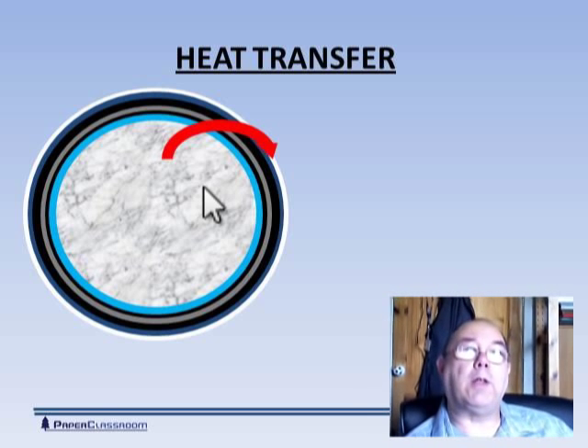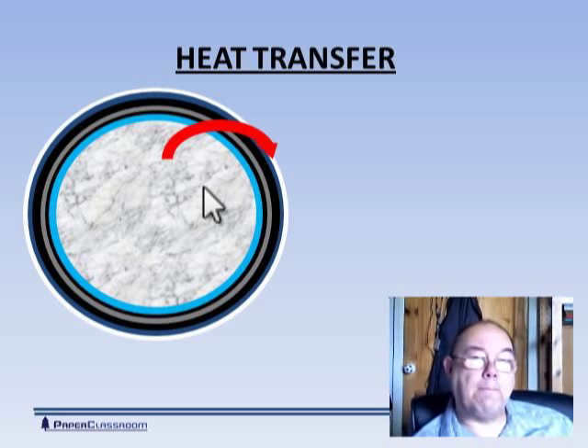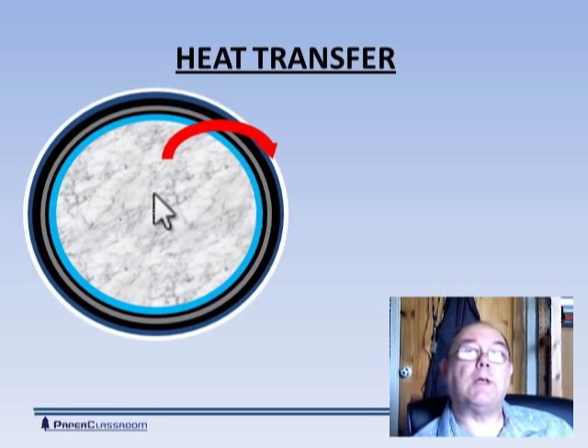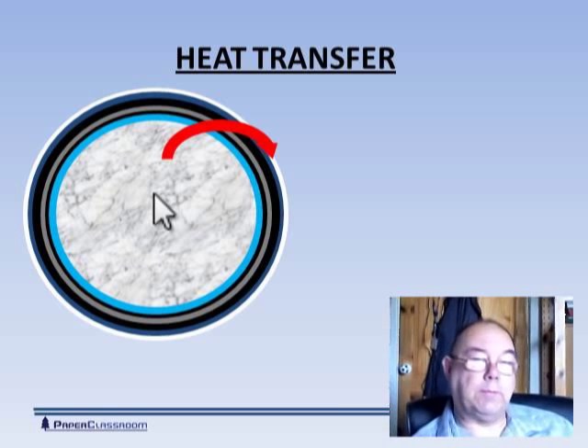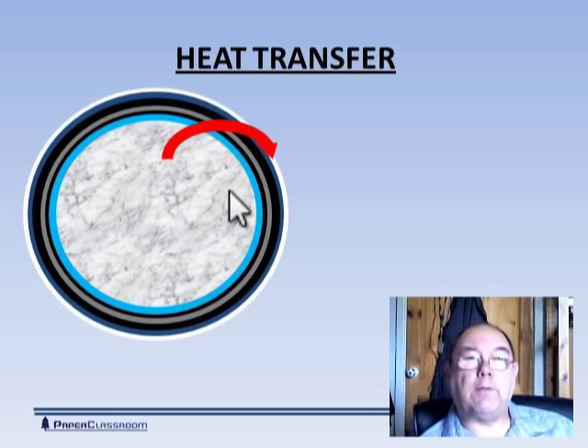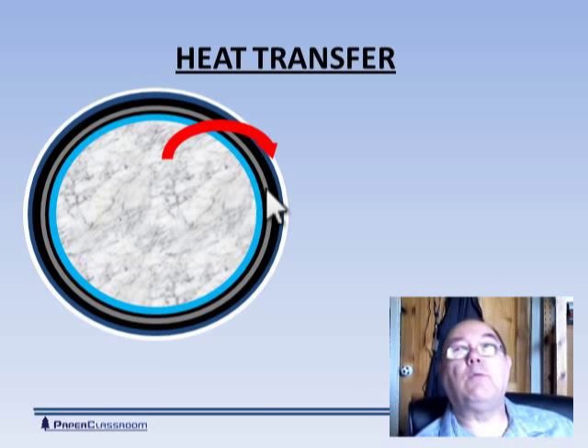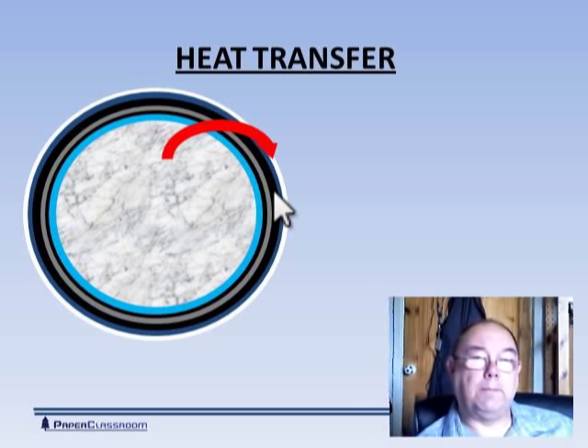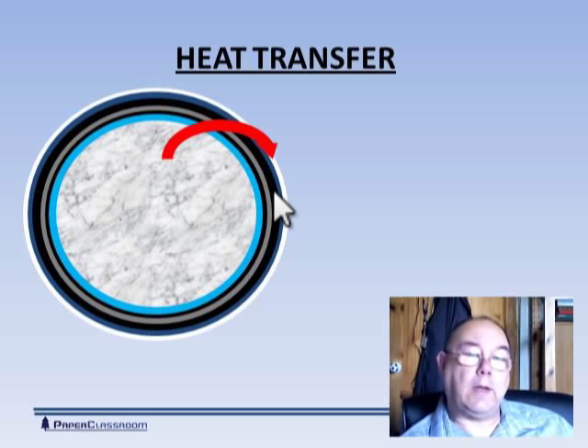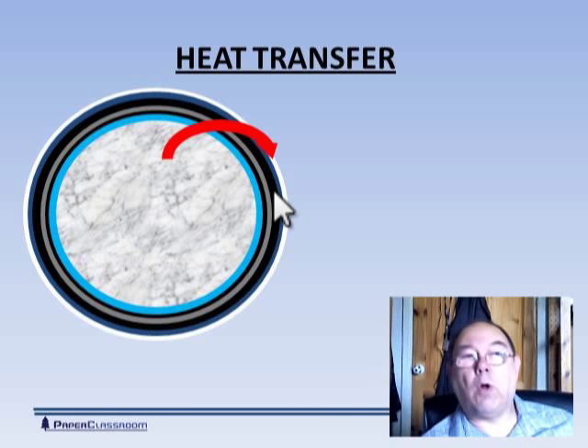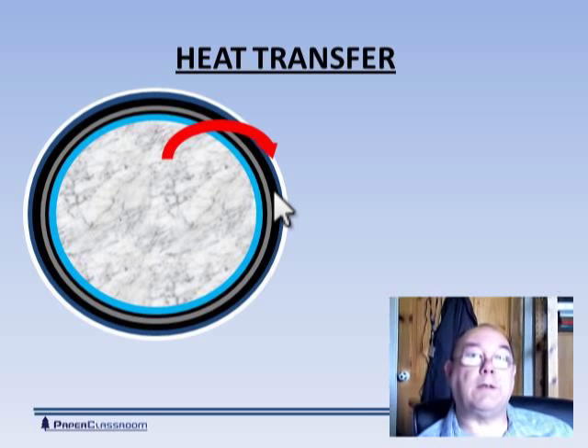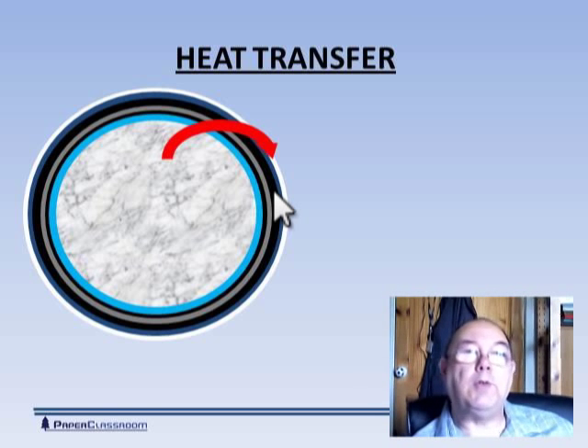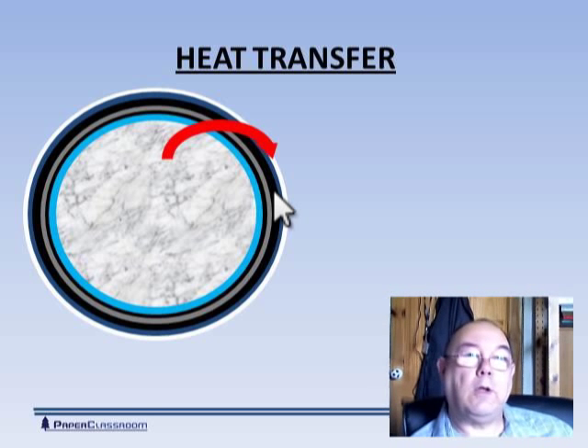Water that comes from the boilers is never 100% pure. There can be carry-over, and this can form scale on the inside of the drying cylinder — this second black ring here represents scale due to carry-over, and that too will restrict the flow of heat. This band represents the shell of the drying cylinder itself, and outside of that we have more scale. As the sheet goes over the drying cylinder, whatever is in the water has the opportunity to come out and stick to the surface. Fibres and filler particles can get pulled out of the sheet, forming a dirty layer on the outside of the drying cylinder, which is also a restriction to heat.